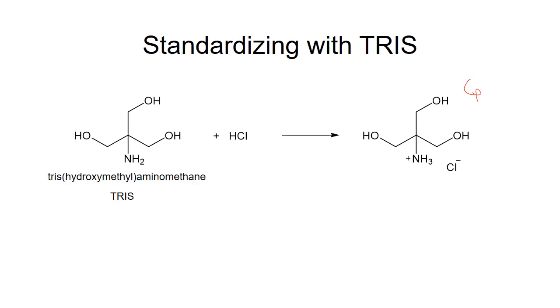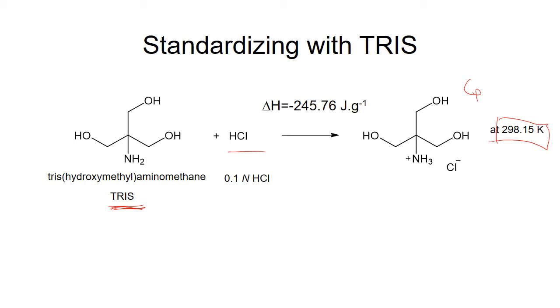We use a reaction with a known enthalpy change: the acid-base neutralization reaction. The acid is liquid hydrochloric acid and the base is tris(hydroxymethyl)aminomethane, or simply TRIS — TRIS is a solid, hydrochloric acid is a liquid. When the HCl concentration is 0.1 M and the temperature is 298.15 K, the reaction enthalpy is 245.76 J/g. So if we use TRIS with mass m, the reaction enthalpy is m × 245.76 J.